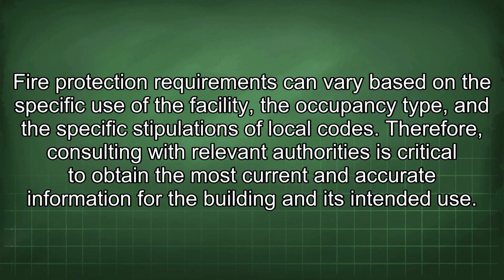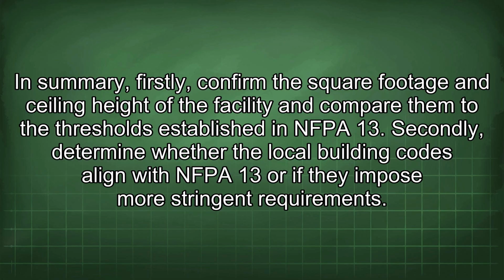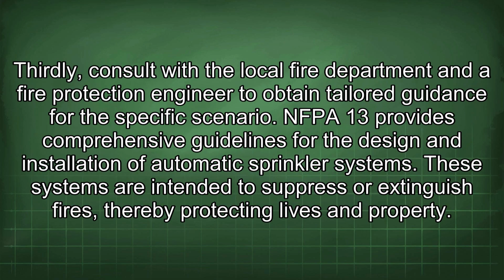Fire protection requirements can vary based on the specific use of the facility, the occupancy type, and the specific stipulations of local codes. Therefore, consulting with relevant authorities is critical to obtain the most current and accurate information for the building and its intended use. In summary, firstly, confirm the square footage and ceiling height of the facility and compare them to the thresholds established in NFPA 13. Secondly, determine whether the local building codes align with NFPA 13 or if they impose more stringent requirements. Thirdly, consult with the local fire department and a fire protection engineer to obtain tailored guidance for the specific scenario. NFPA 13 provides comprehensive guidelines for the design and installation of automatic sprinkler systems.